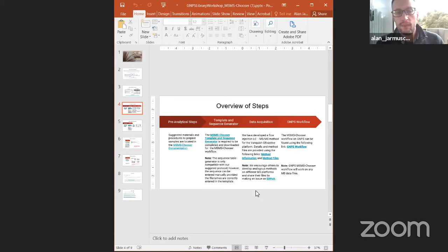This is built on a Vanquish Q Exactive platform. Those are Thermo instruments, and it's a single injection into a flow of solvent from the LC. For every sample, the autosampler comes along, takes up a couple microliters of sample, injects it into a flow of 50% methanol, and then the mass spectrometer does its MS analysis. Then it just continuously does this, and that's what really makes it so fast.